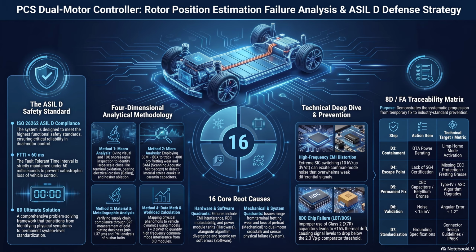Right. If the SMO mathematical model assumes the stator resistance is still 20 milliohms, but the physical reality is 30 milliohms, the internal state observer subtracts the wrong voltage drop from its calculations. The matrix diverges. The calculated angle drifts further and further from the true physical angle until the magnetic field vectors misalign completely, resulting in a total loss of torque. So the backup parachute essentially just dissolves midair. That's a great way to put it, yeah.